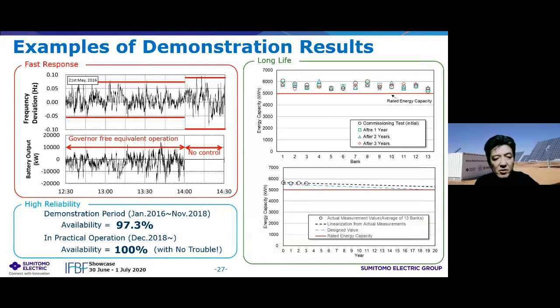The figure on the right shows the results of capacity tests conducted each year. The system consists of 13 banks, and no significant deterioration has been observed in any of them. Linear approximation from the yearly capacity measurement data shows a slight decrease in capacity per year. The system keeps rated capacity for 20 years, and there's no need to replace the cell stacks.